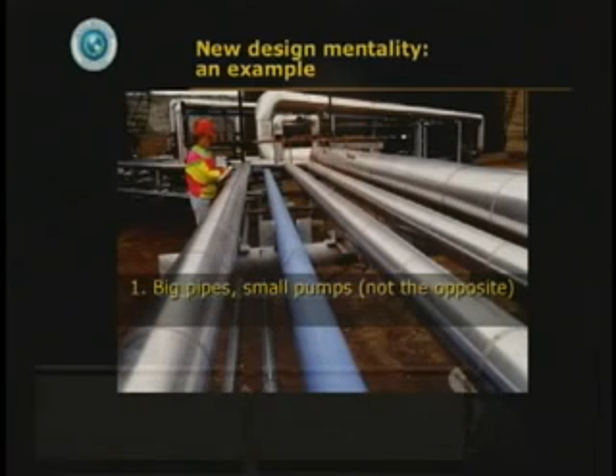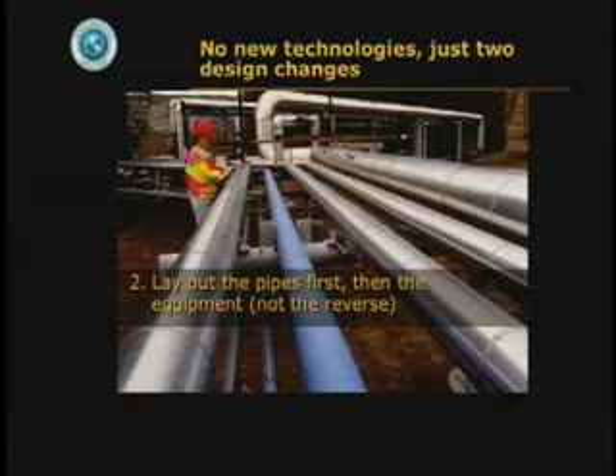The other change in design mentality was even simpler and more difficult: lay out the pipes first, then the equipment. What normally happens is that the tanks and boilers go in some arbitrary, traditional, or convenient place, and then you call in the pipe fitters and say, please come connect point A to point B. But by then, A and B are rather far apart.